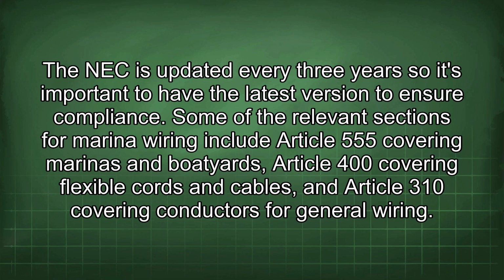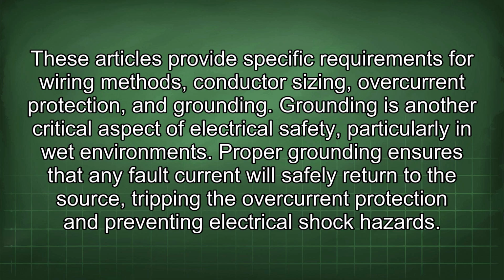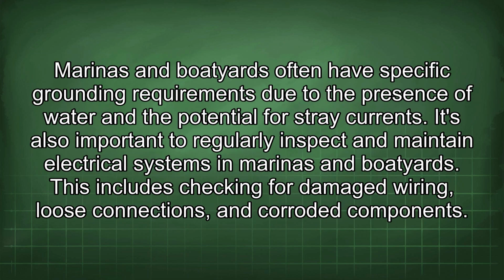Some of the relevant sections for marina wiring include Article 555 covering marinas and boatyards, Article 400 covering flexible cords and cables, and Article 310 covering conductors for general wiring. These articles provide specific requirements for wiring methods, conductor sizing, overcurrent protection, and grounding. Grounding is another critical aspect of electrical safety, particularly in wet environments. Proper grounding ensures that any fault current will safely return to the source, tripping the overcurrent protection and preventing electrical shock hazards. Marinas and boatyards often have specific grounding requirements due to the presence of water and the potential for stray currents.